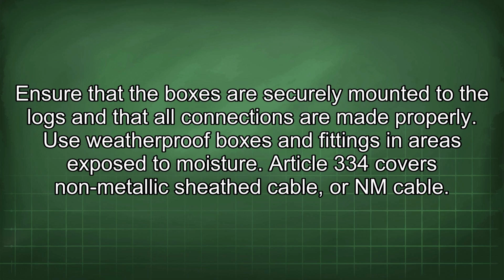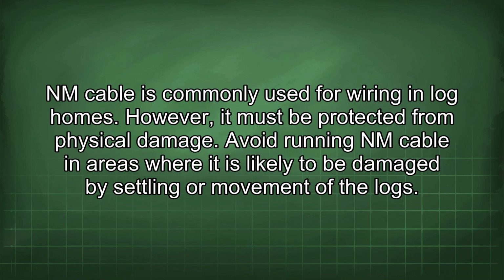Article 334 covers non-metallic sheath cable, or NM cable. NM cable is commonly used for wiring in log homes. However, it must be protected from physical damage. Avoid running NM cable in areas where it is likely to be damaged by settling or movement of the logs.